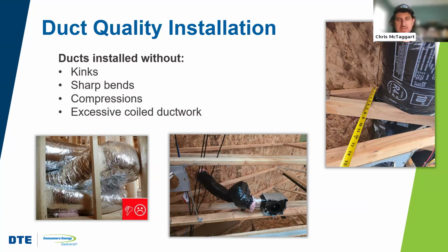Michigan is not a huge flex duct market, but certainly it is used by some contractors. And especially with flex, you can't just wing it, because it bends in all different types of crazy directions. So if it's able to, then I'm fine to do it that way? No, that's not correct. We want straight ductwork. We want non-compressed ductwork. We want ductwork to be installed where it's not tied into a knot or crushed by a framing member or a plumbing pipe or something like that. So basically, ductwork has to be installed without excessive degradation to its ability to deliver airflow.